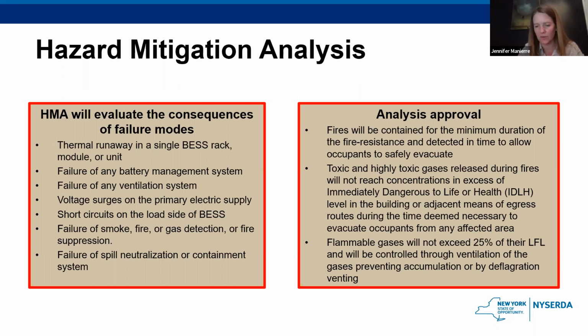So you're not saying that a fire can't happen. You're saying if fire does happen, you want to make sure it's going to be contained long enough to get people out safely. Also, it needs to show that toxic and highly toxic gases that might be released during the fires will not reach concentrations in excess of those levels that might be dangerous to the life or health of folks in the building before they have time to get out of the building. And then finally, that any flammable gases will not exceed 25% of the lower flammability limit and will be controlled through ventilation. So preventative measures, right? And if the hazard mitigation analysis shows that all 3 of those things are met, you can proceed. And again, this is only for those larger systems over 600 kilowatt hours.